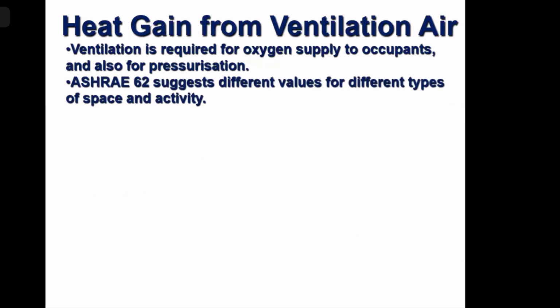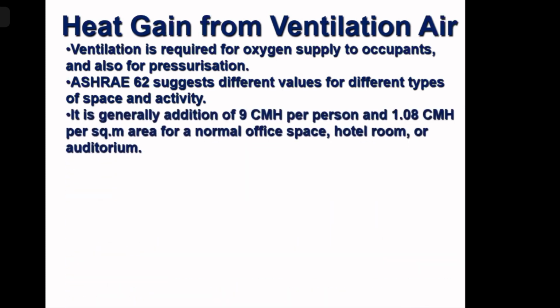Heat gain. Now, before we go for heat gain from the ventilation air, we must know how much ventilation air we should take. ASHRAE 62 has suggested how much ventilation air we should give for various applications. For general office space, hotel room, or auditorium, we should give 9 cmh per person, or 2.5 liters per second per person for breathing purposes, and additionally 1.08 cmh per square meter of area, or 0.3 liters per second per square meter of area, for making the room overpressure, considering a standard amount of leakage.